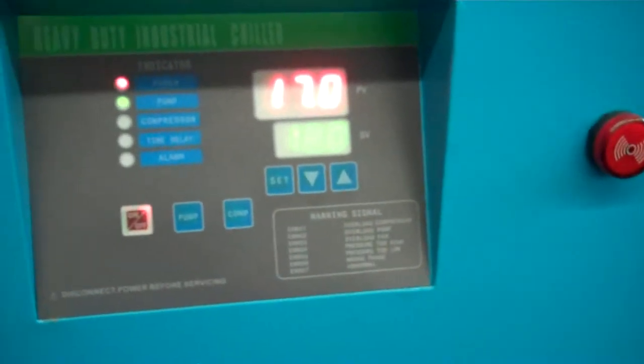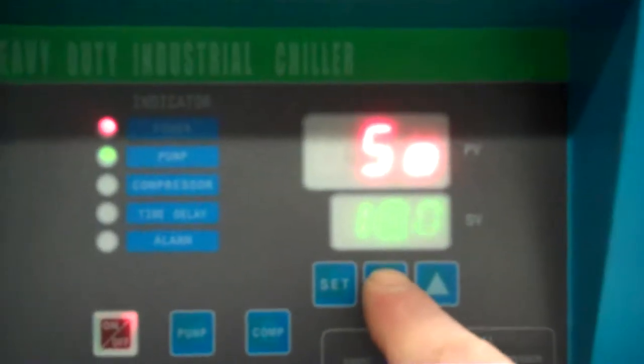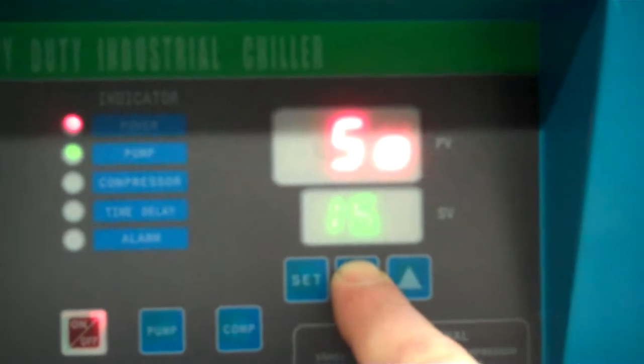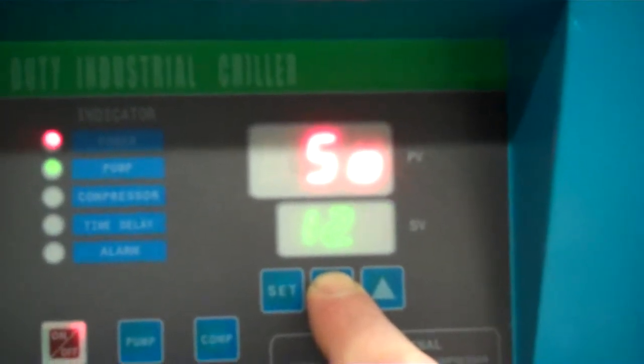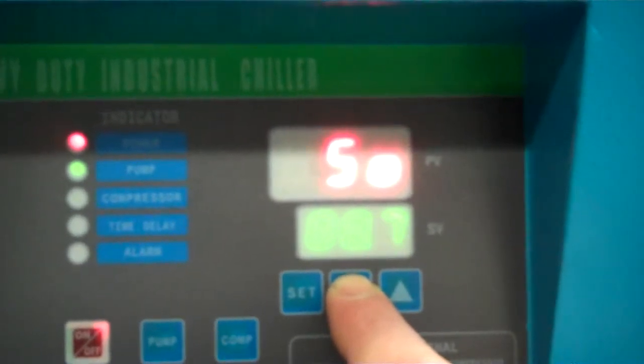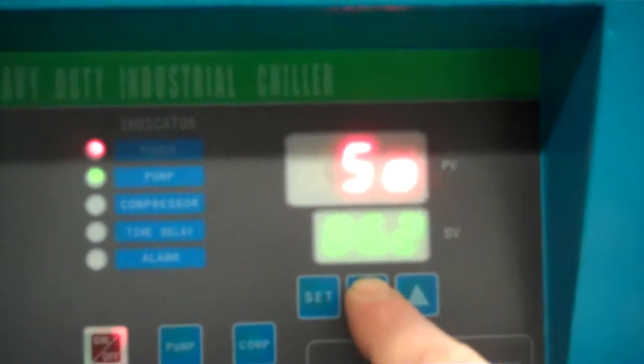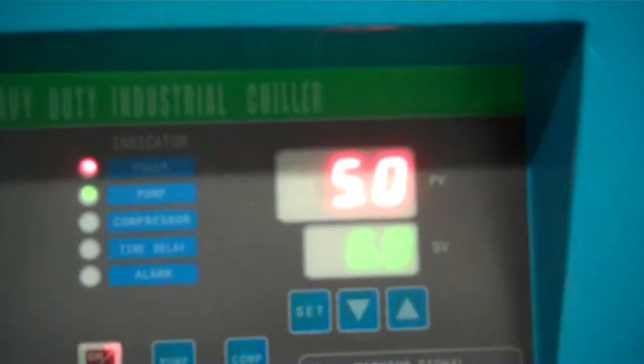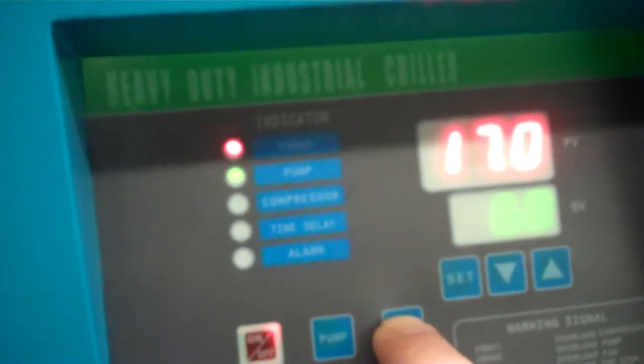The set point range on this is 6 degrees C to 25 C. The red is the process value. The green number is the set point value. We're going to go ahead and chill down to 6 degrees Fahrenheit by pressing set. I'm sorry, 6 degrees centigrade is what I meant. And press the compressor button next, and there'll be a time delay before we start chilling.